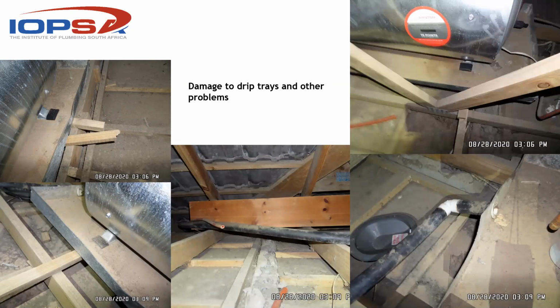That's for sure. It was a couple of months ago I took these pictures. The overflow has got a backfill. It is the wrong material, and it simply is not adequate. It will not fulfill the function. And we're going to get into what the expected performance of a drip tray is supposed to be in a minute. Well, the next slide actually.